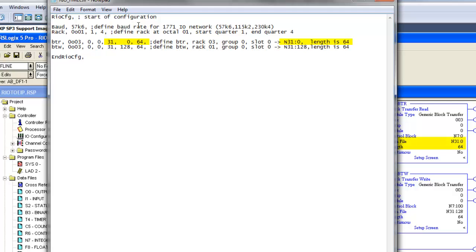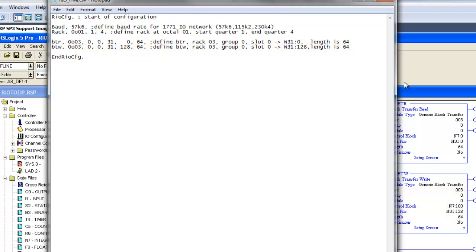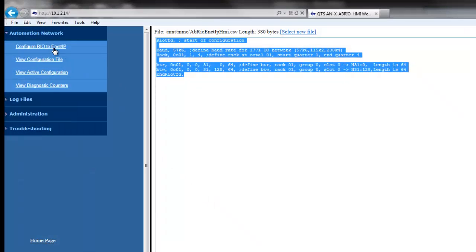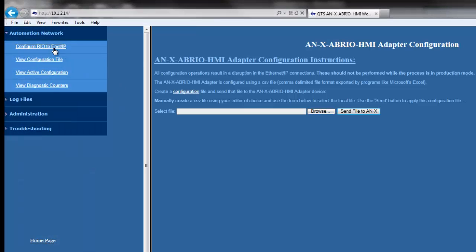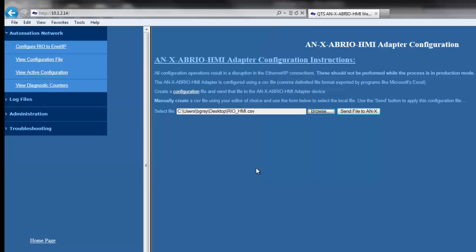The BTW is rack 3, group 0, slot 0, writing from N31:128 for a length of 64. We'll change the rack from 1 to 3 on both block transfer read and write. Now we'll save the CSV file and download it to the AN-X module by clicking on Configure RIO to Ethernet IP, select Browse, choose the CSV file that we altered, and choose Send File to AN-X.